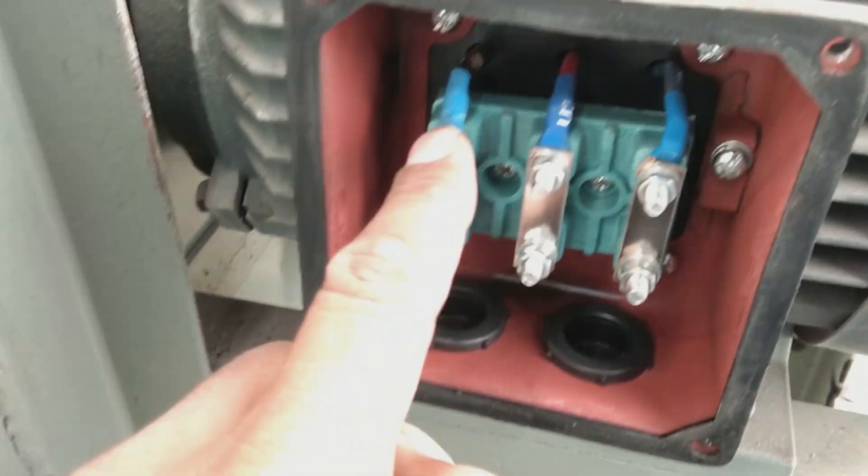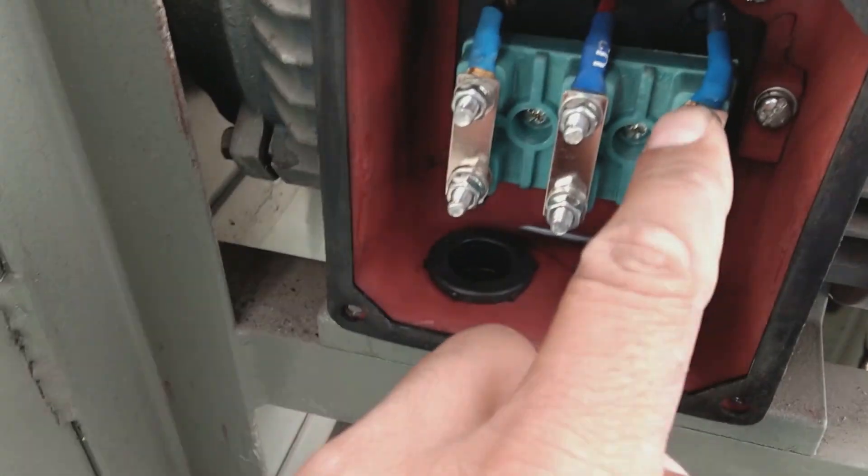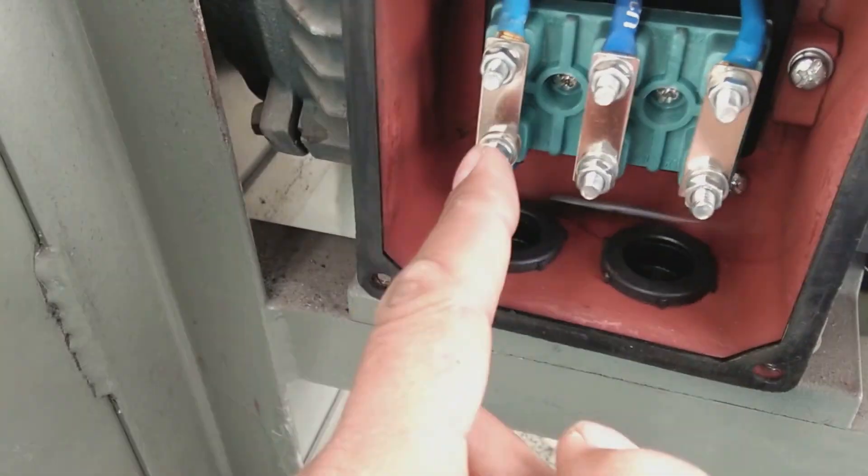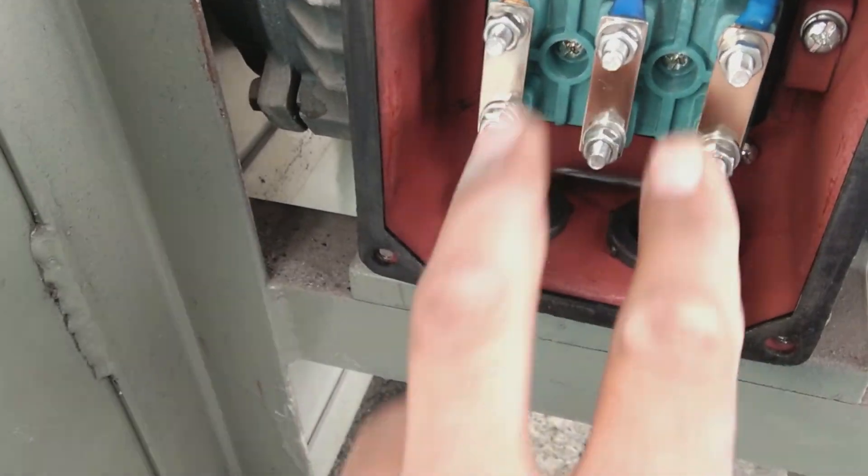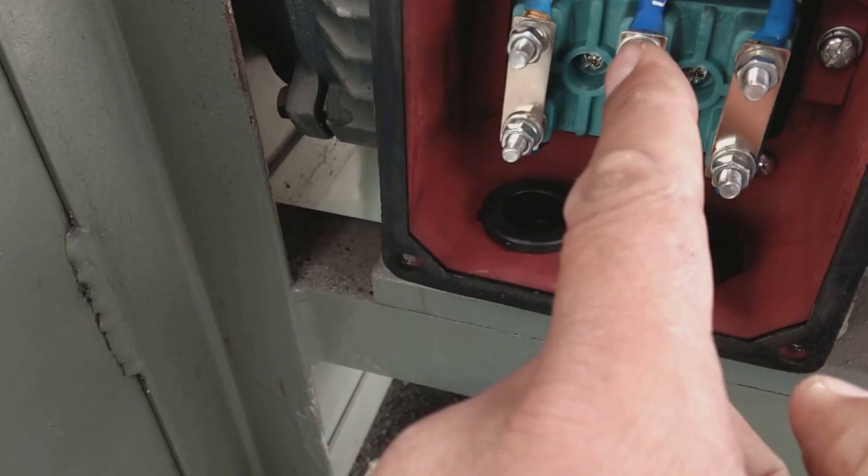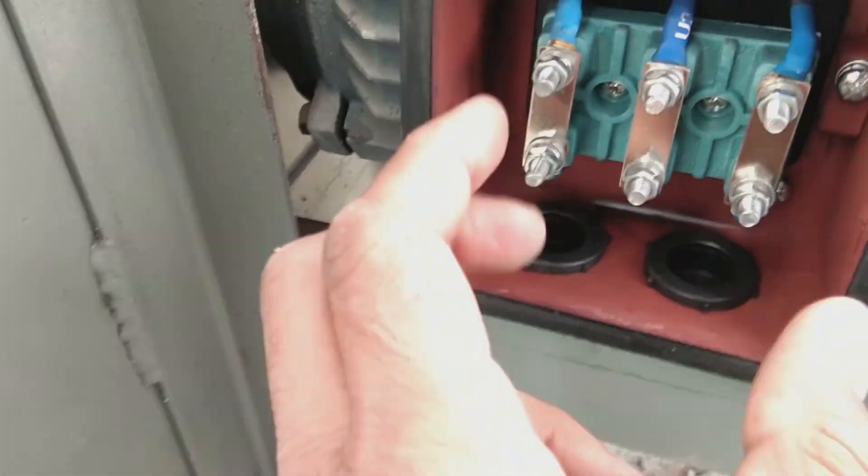Now we're coming to the terminal box. You can see these three plates or jumpers, these bus bars, are connected in one line. You'll connect the three-phase supply here. When they're in one line, it means this is delta connected.